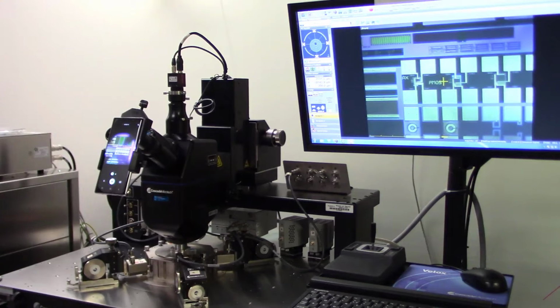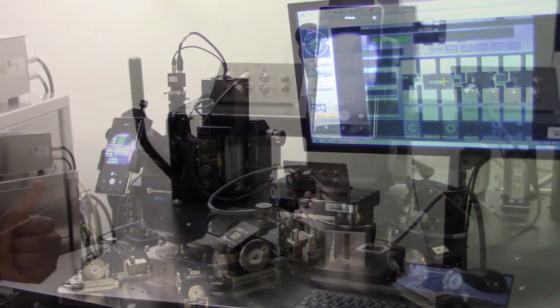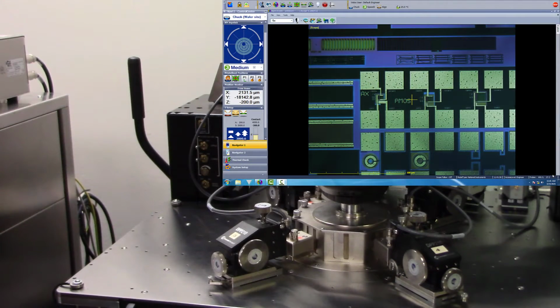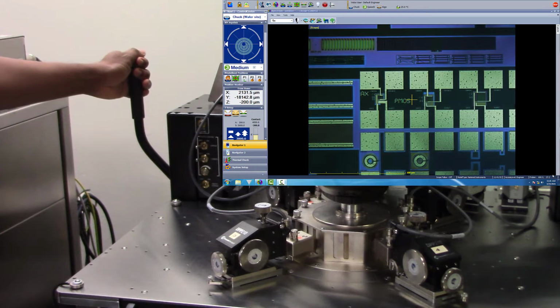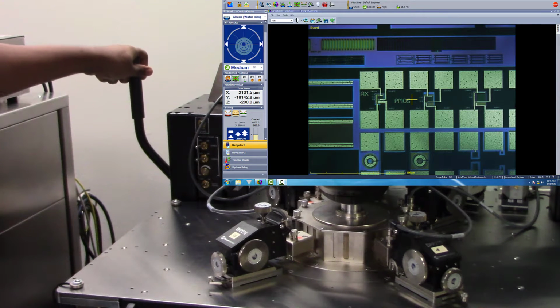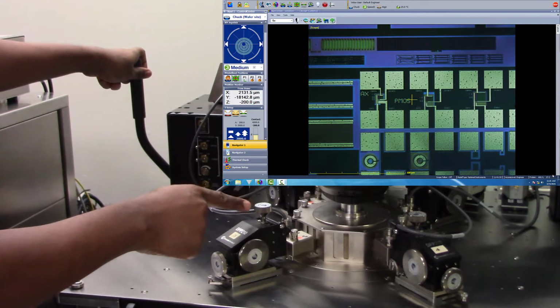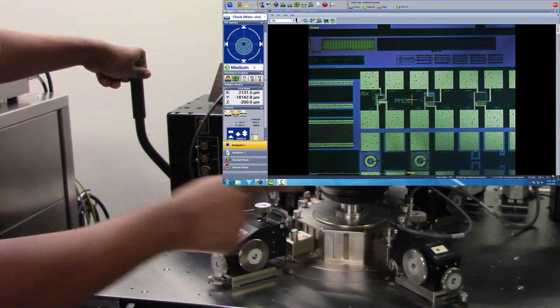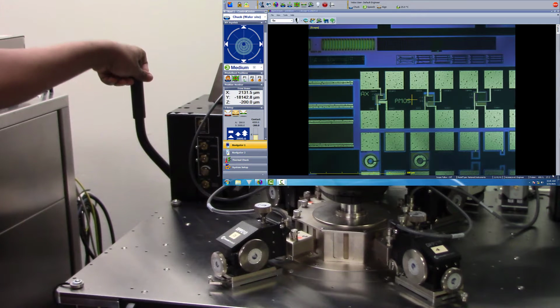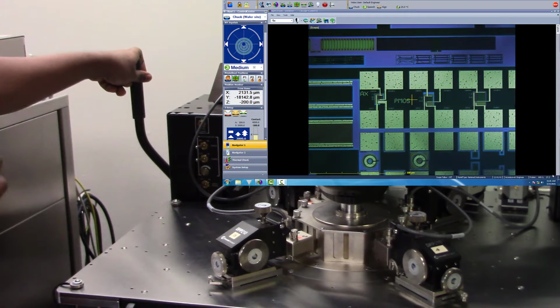So basically what we need to do first, after installing or inserting your device or sample, just like we have over here on the screen, is use the platen lever to land our sample. While we're trying to land our probe tips on our sample, we're going to make use of the platen lever over here, and we're going to make use of the Z position on your micro positioners to make sure that we do not crash the probe tips into our sample.